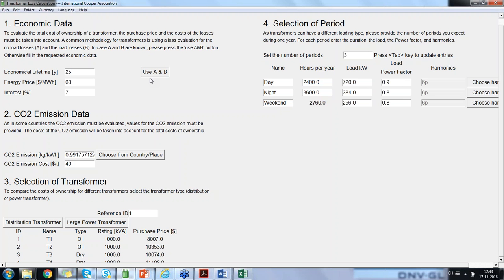So there are possibilities to use transformers to reduce your harmonic content. But still the harmonic content will flow within some parts of the winding of the transformer, so make sure that you still add those values as well when you specify the transformer. But there are possibilities to reduce it. I think we have done it in some industries, and also with traction for trains. You will see them very often used over there to reduce the harmonics outside of the loading of that equipment.